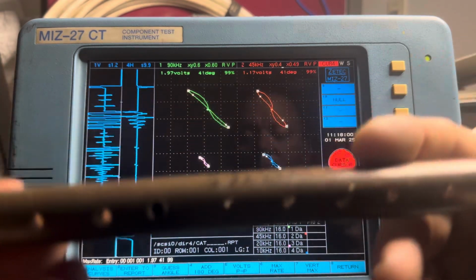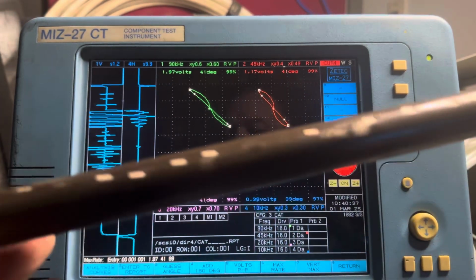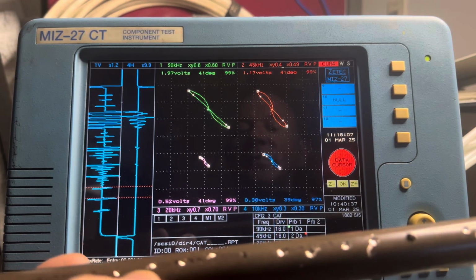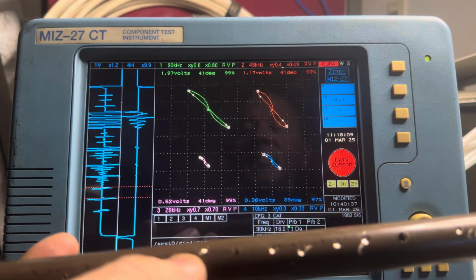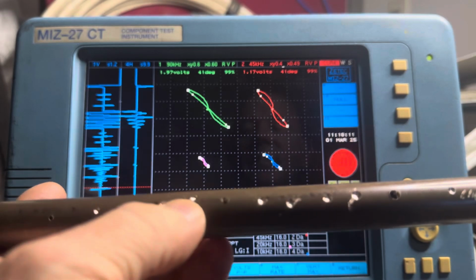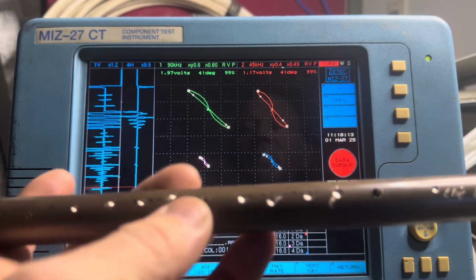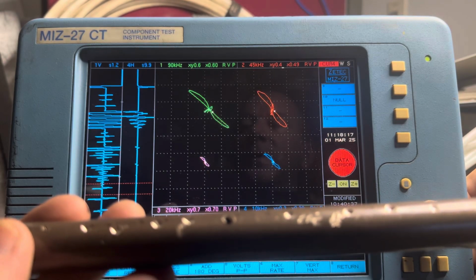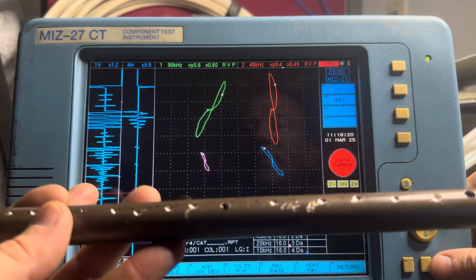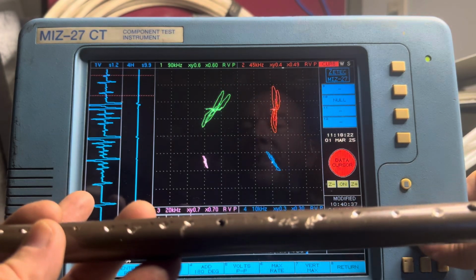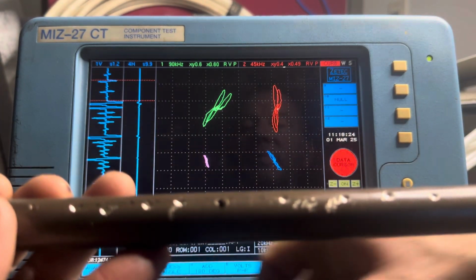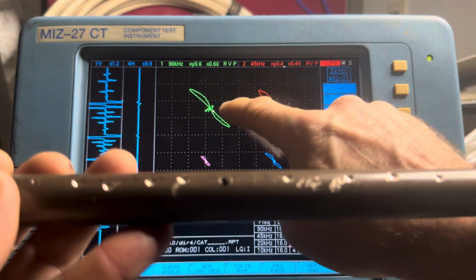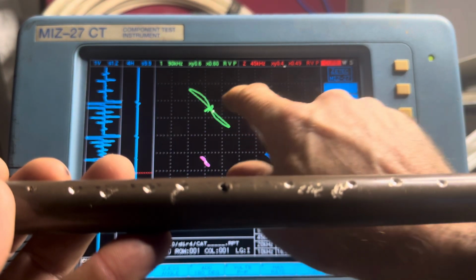This one happens to be 0.052 inches in diameter. Again, here's where it starts to get busy. So I'm going to have a series of 4 flat bottom holes, each one a little bit deeper than the last, and then that same drill bit, but a through-wall hole. So let's see if we can see the 4 little ones. It's probably easier even to see some of them on the strip chart here. See 1, 2, 3, 4, and then a big one. So the tiny one is kind of right in the middle there. You can barely see it.